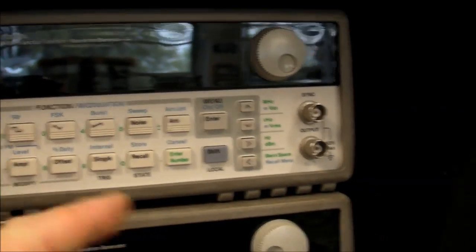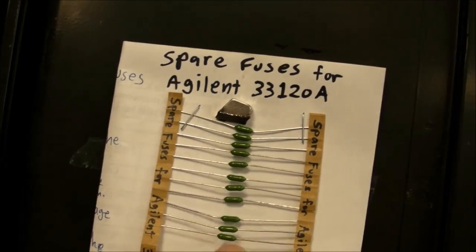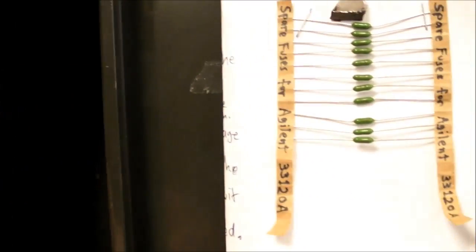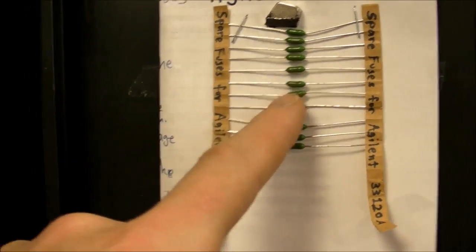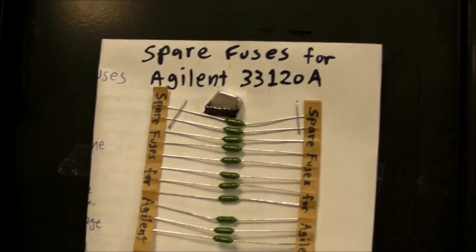Another thing I keep in here is spare fuses for these Agilent 33-120s because probably once or twice a semester I have to replace one of the fuses on the 50-ohm output. Somehow that gets blown. I guess students mistakenly hook up their 15-volt power supply to it or something like that. Somehow the fuse gets blown once or twice a semester and so I got to pop it open and solder on a new fuse onto the circuit board.